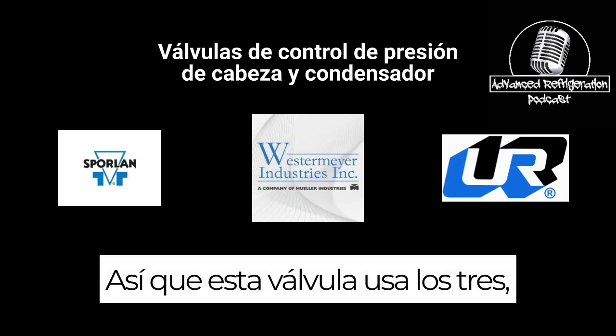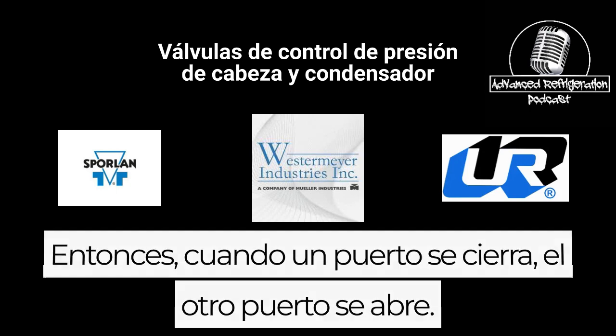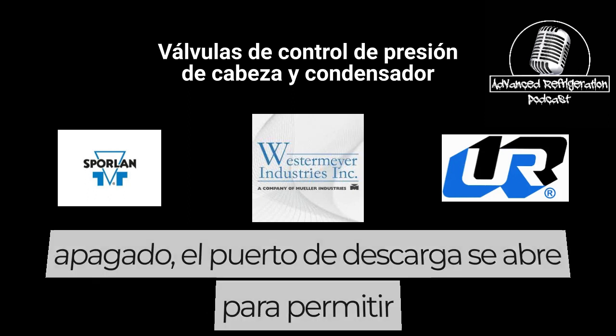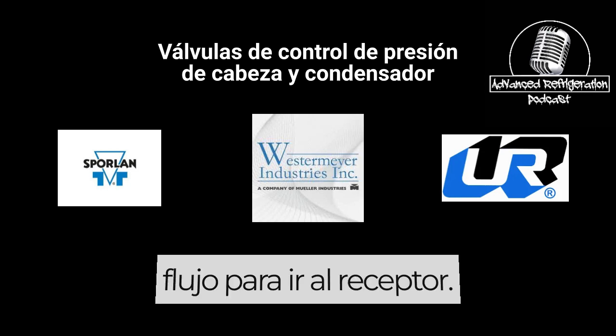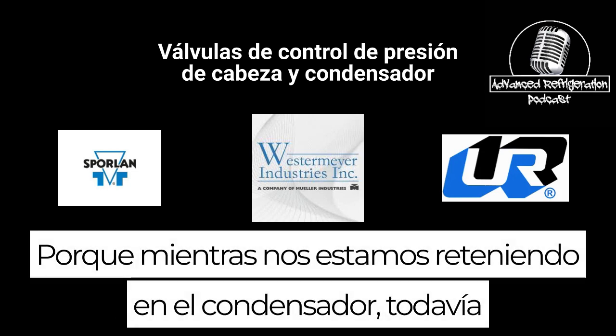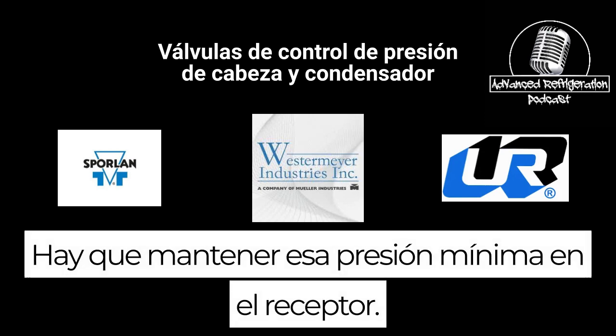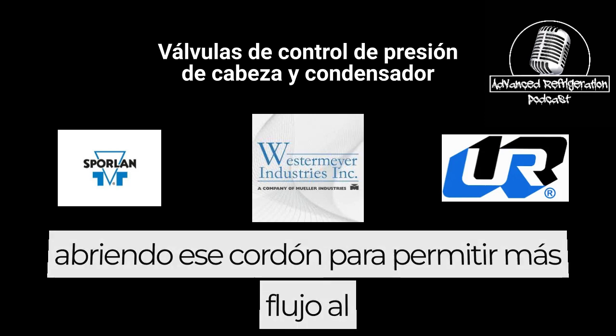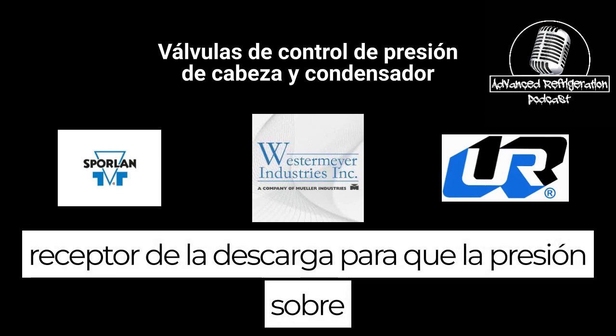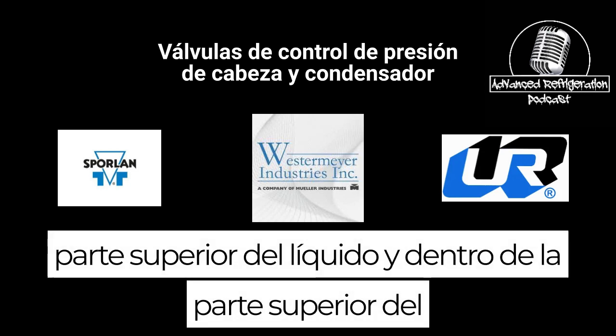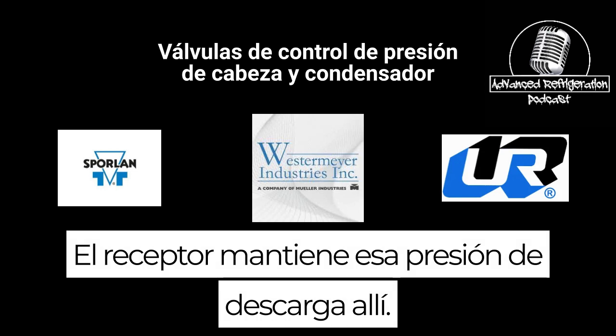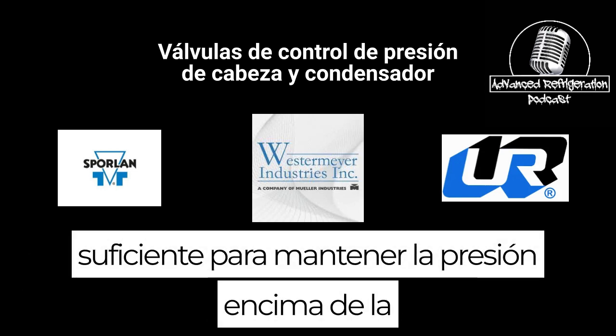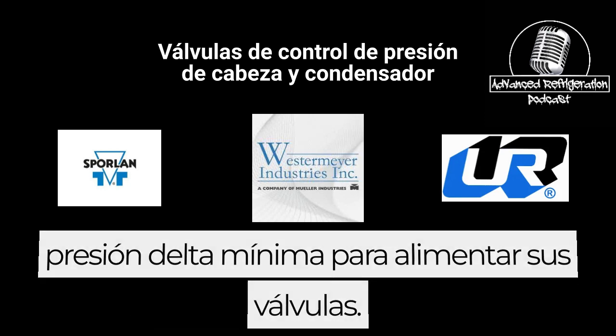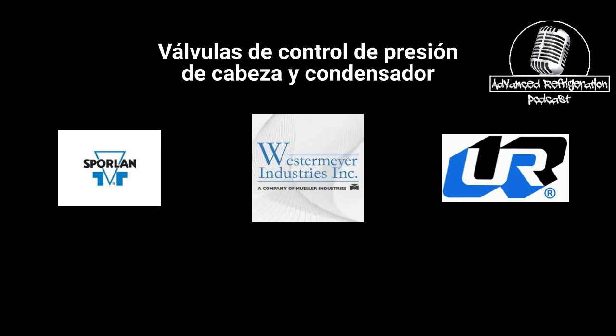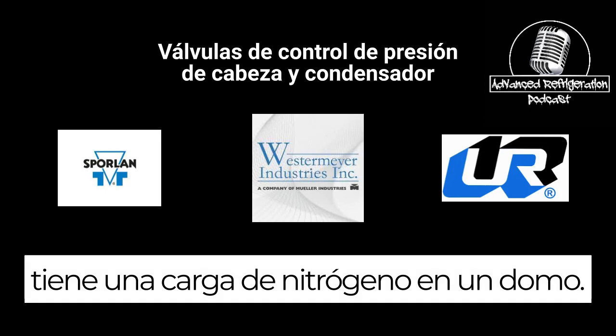So this valve uses all three of these, and it is essentially a three-way valve. As one port gets pushed shut, the other port opens. As the condenser outlet port gets closed off, the discharge port opens to allow flow to go to the receiver, because as we're holding back in the condenser, remember, we still have to keep that minimum pressure in the receiver. As it's holding back in the condenser, it's opening that port to allow more flow to the receiver from the discharge, in order to get pressure on top of the liquid inside the receiver and keep that discharge pressure in there. It's not a ton of it, but it's enough to keep the pressure on top of the receiver, keep your liquid flowing, and keep your minimum delta pressure to feed your valves. The way this valve works is it has a nitrogen charge in a dome.